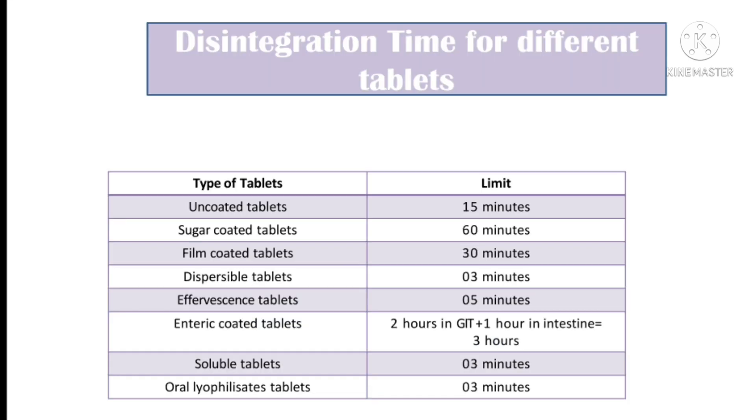Now the disintegration time for different tablets are as follows: uncoated tablets 15 minutes, sugar coated tablets 60 minutes, film coated tablets 30 minutes, dispersible tablets 3 minutes, soluble tablets 3 minutes. The limit is if one or two tablets fail to be disintegrated, test is repeated using 12 tablets.